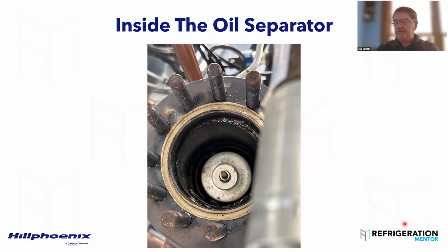Well, first thing is, if you're new, it's your first CO2 rack, don't be afraid to ask questions. Don't be afraid to get in there and actually help. Hey, what can I do? What does this do? How do I do that? How do I put oil in here? You know, I've had guys fill up an oil reservoir with 500 pounds of pressure on it. And that's what I like to call a learning experience. I let him do it. He put his first can in. And then I said, well, you know, me, I would isolate it and vent the pressure out. Think about what you're doing.